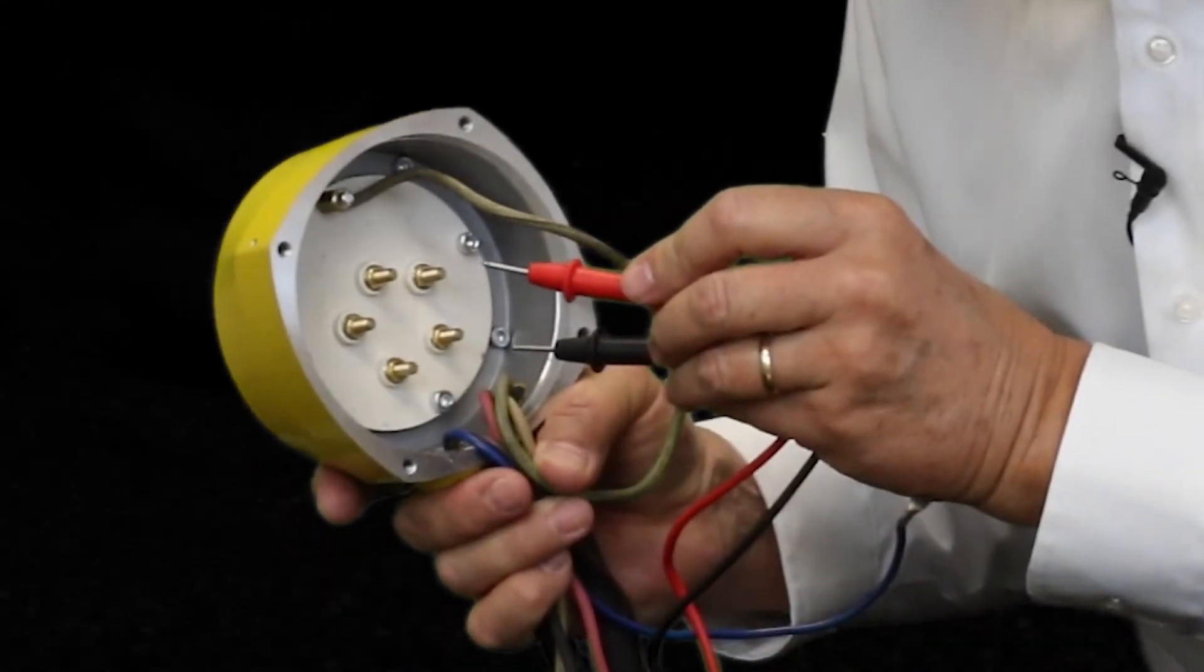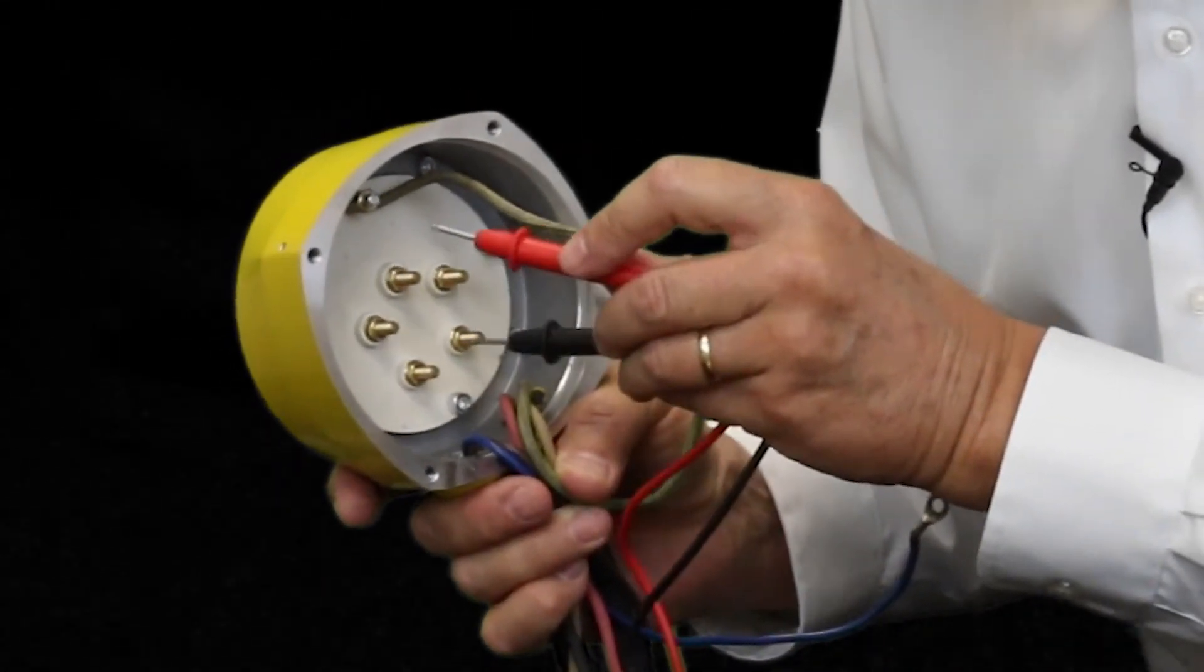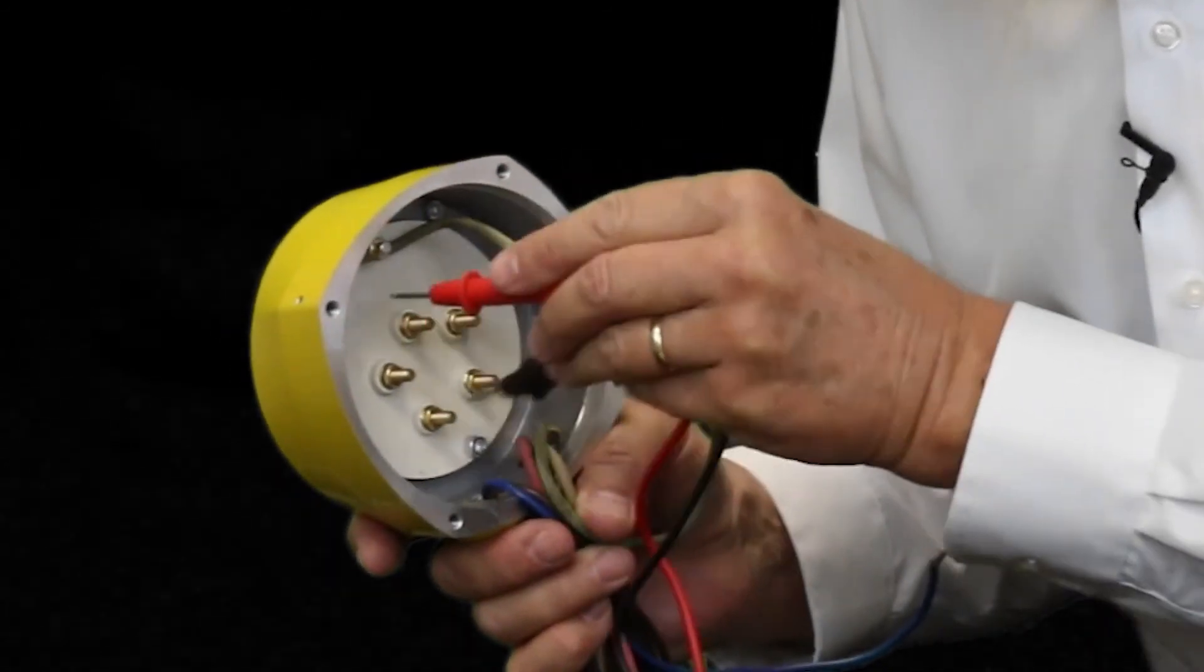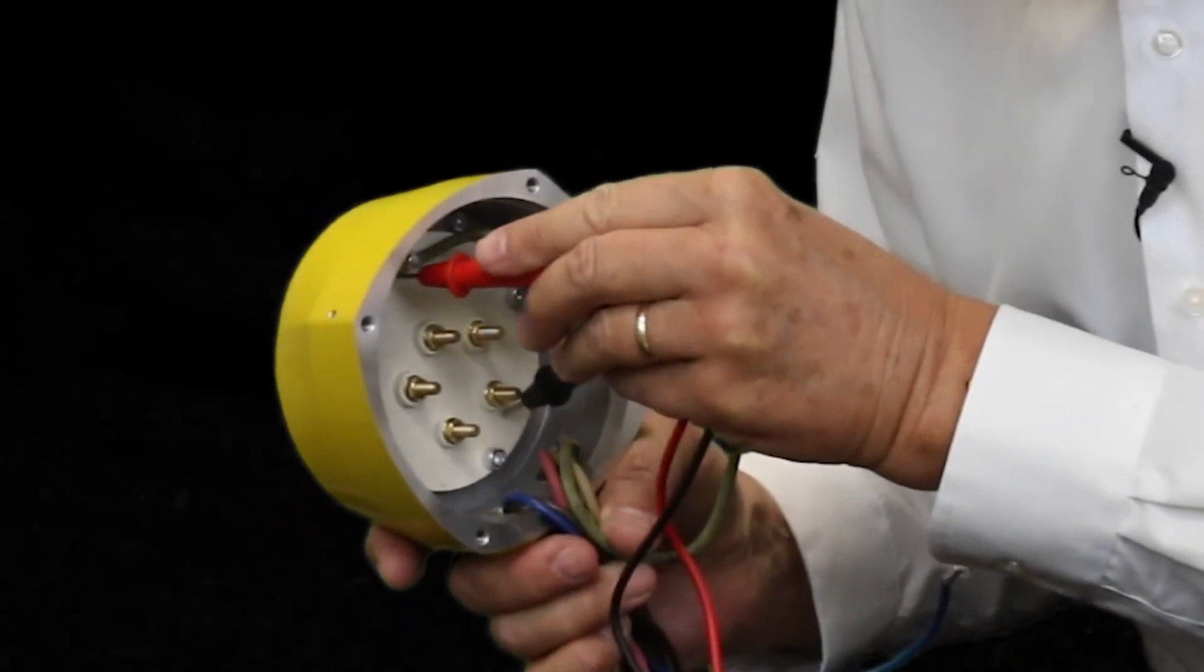And here's how you check the resistance to ground between the thermal protection switch and ground. Touch the probe to T1 and the ground probe.